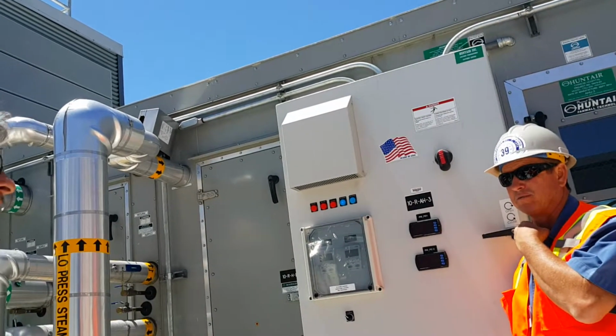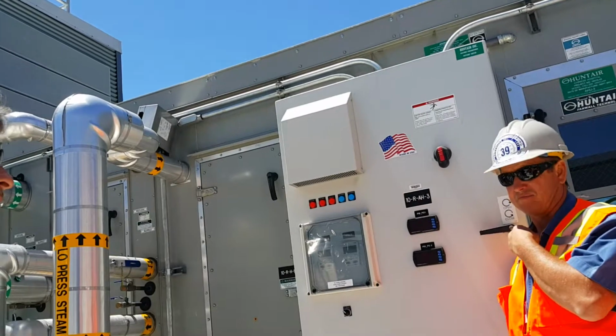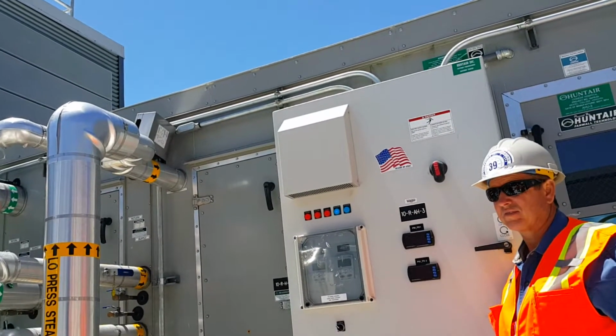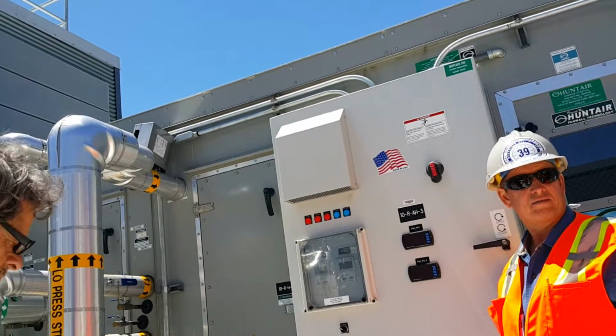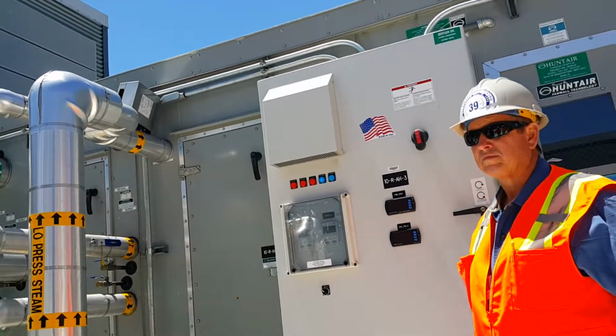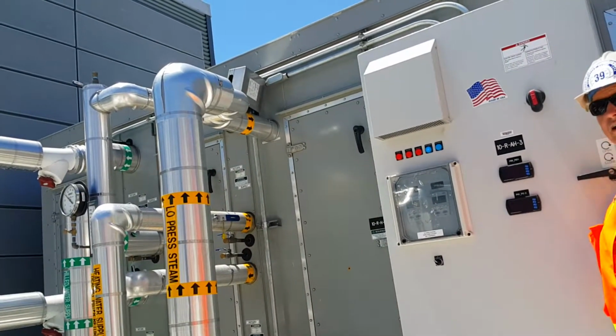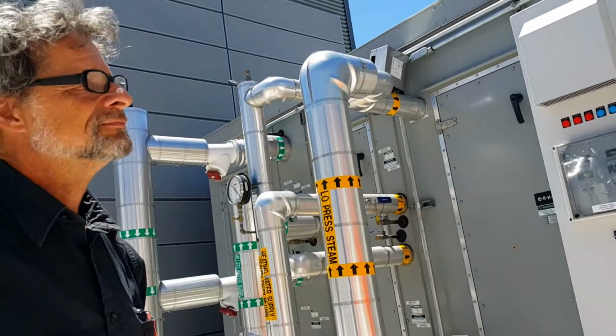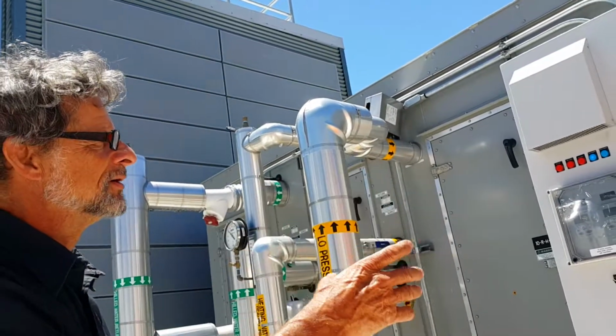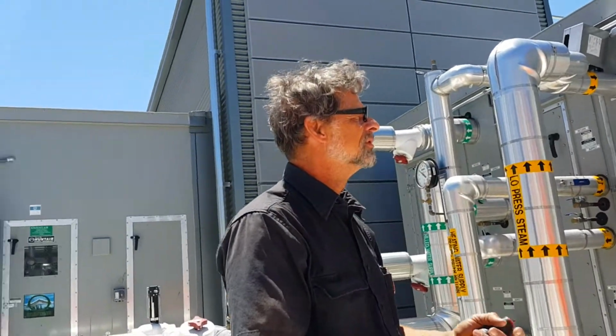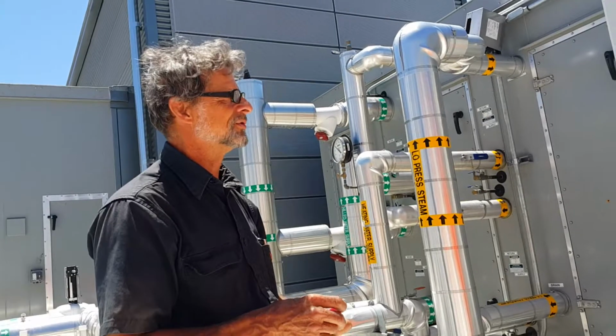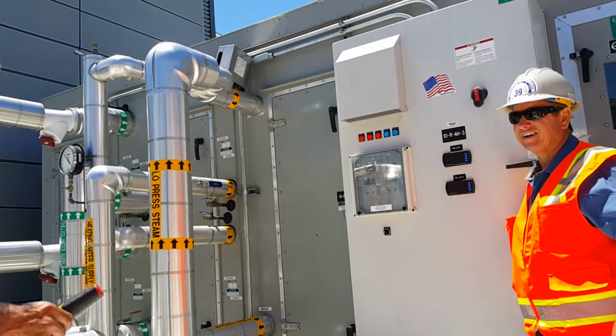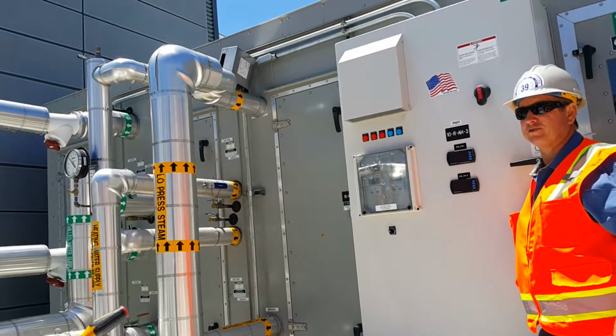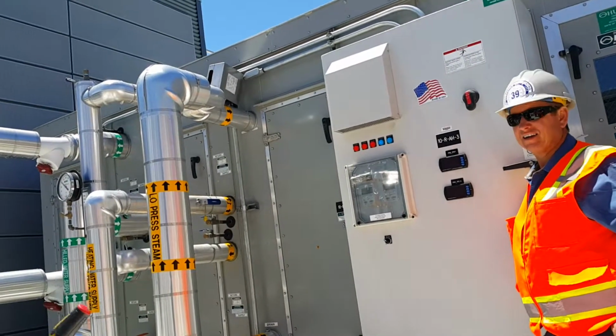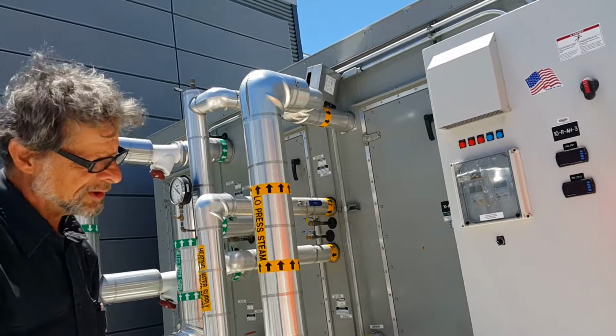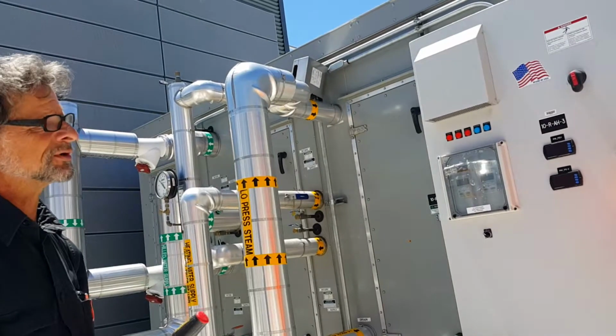That happens because the state said to put them in. It's a requirement, I think, of a state regulation or something. But nobody needs them in the Bay Area, so they just turn them all off. Yeah, they got a hundred and some of them over in that Kaiser high rise in Oakland they just put up. A hundred and some dry steam humidifiers, each one in its own little tank, in recovery rooms, in bedrooms, in operating rooms, and all those things. Talk about a maintenance headache. Would you replace or clean? That's almost a full-time job.